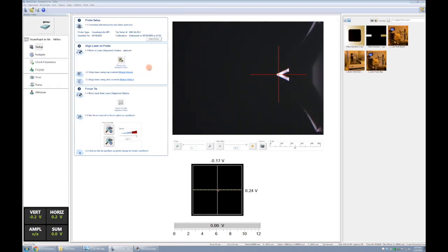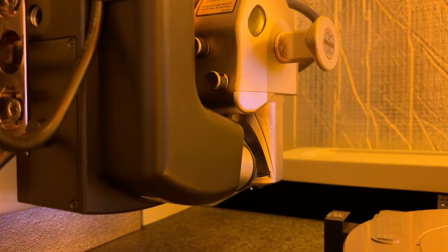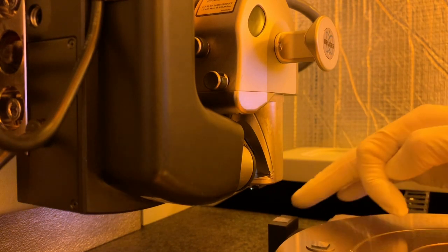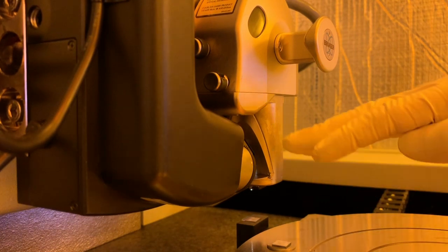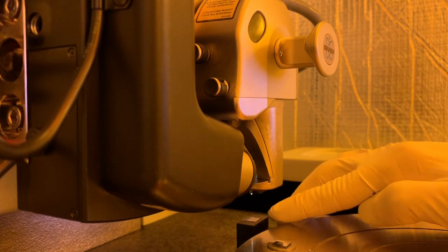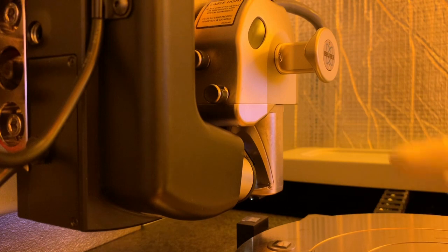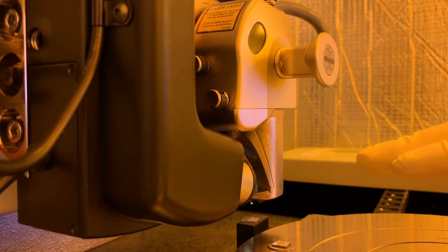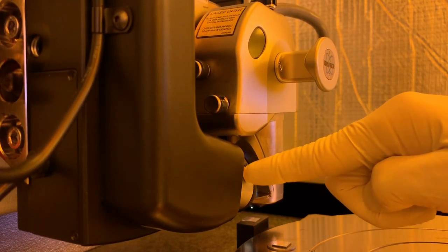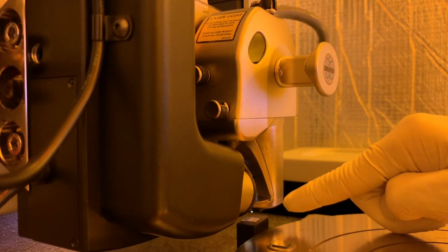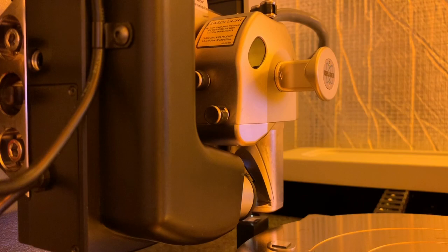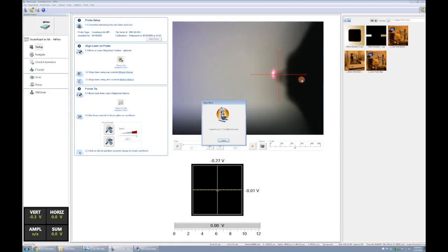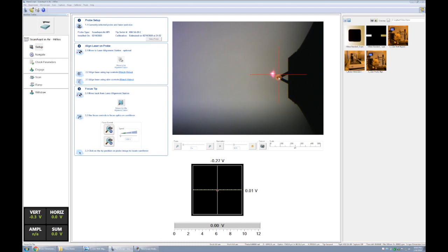Okay, and next we'll click to move to the alignment station, and say yes, that we're not using the fluid cantilever holder, which would otherwise be incompatible and unsafe to move to the station with. And over here we see this is the alignment station, and it's moving directly underneath the scanner, and then the scanner will start to lower until it gets exactly one millimeter from the top of the station. The station itself is basically a reflective plane, and it's a way for us to ultimately visualize where the laser is with respect to the cantilever. Now this is the objective lens for the optical microscope. We're going to see that's going to push in once this gets to one millimeter. And as the objective lens pushes in, we see it goes from an image directly of the cantilever to a silhouette image of the cantilever.